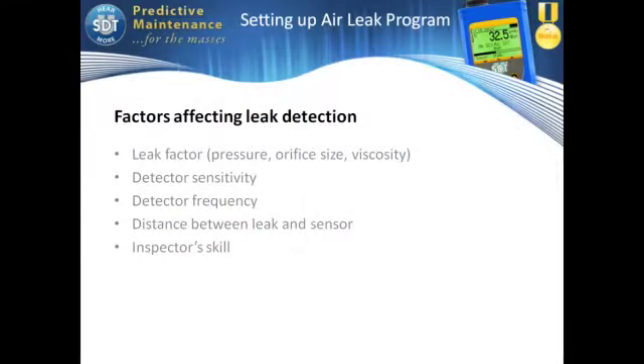If I'm thinking about setting up a leak detection program, there are things I need to consider: the pressures, sizes of orifices, viscosities of the gases I'm using, how good my instrument is at detecting, how sensitive it is, what measurement frequency am I going to use, distances - how far away can I get, how near can I get - and do I have the skill as an inspector to deal with that?